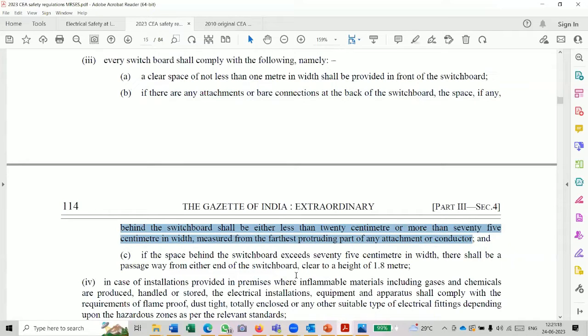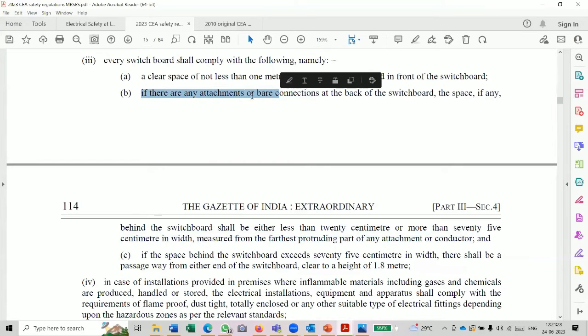Yeah. Actually, he carefully read the regulation 39.3b. There is a wording: if there are bare conductors, the question is bare conductors. In normal switchboards, bare conductors require attention. Frequent opening, rear opening, open doors will be available. People have to go and do some termination or maintain something. In that condition, how can you restrict the entry to less than 20 centimeter? That is not correct. The wording, bare connection, should not come into this area.